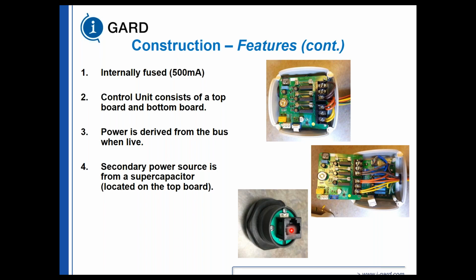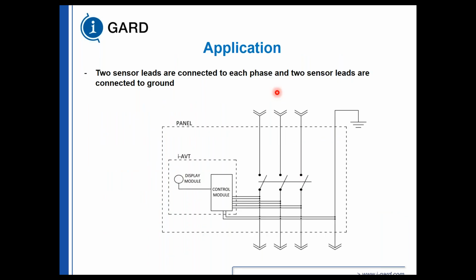And a Cat5 cable connects the display unit to, I don't know if you can see it, that part of the control unit. So there are 2 sensor leads connected to every phase: 2 wires on A, 2 wires on B, 2 wires on C, 2 wires to ground. And this is to verify that it's properly connected, and this is a requirement of UL 1436. I didn't put the wires in there, i-Gard didn't put the wires in there because it's more cumbersome. We have to put the wires in there to comply with 1436.